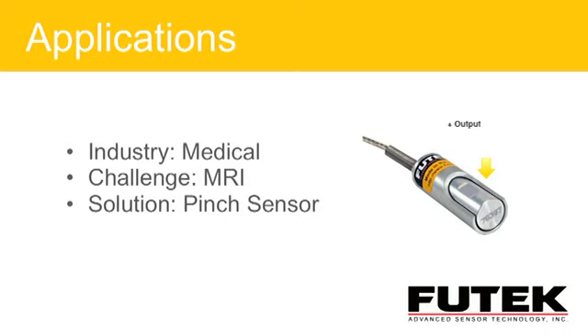One of their challenges was having to use this pinch force sensor in an MRI field. In an MRI field you have to be real careful—everything has to be non-magnetic, and there are some decent flux fields going on. So we had to come up with a product where it was a pinch force for the operator, sandwiched between normally their thumb and hand, measuring that force or tactile feel during the pinch. We had to use completely non-magnetic materials and watch the components used inside.